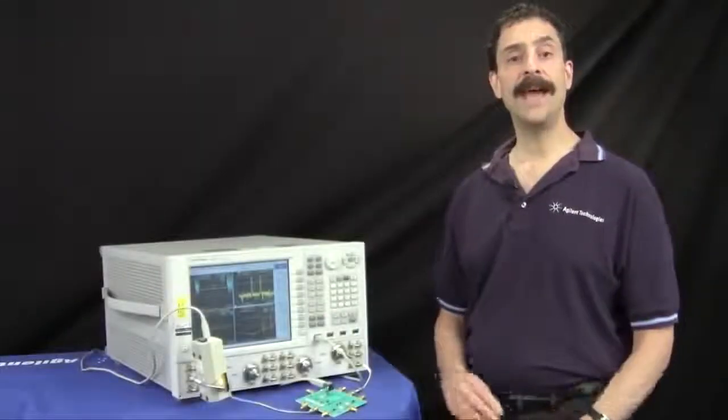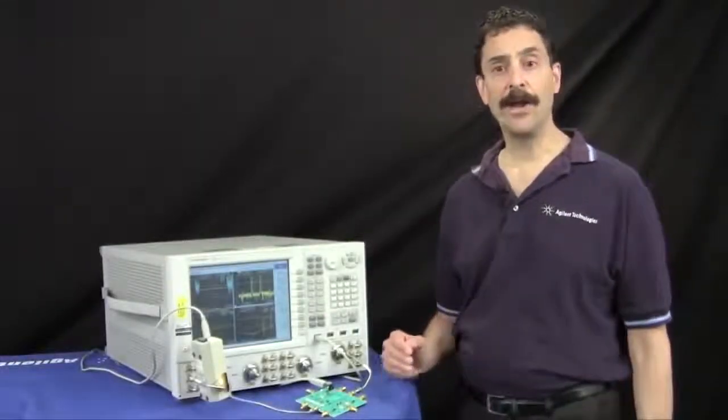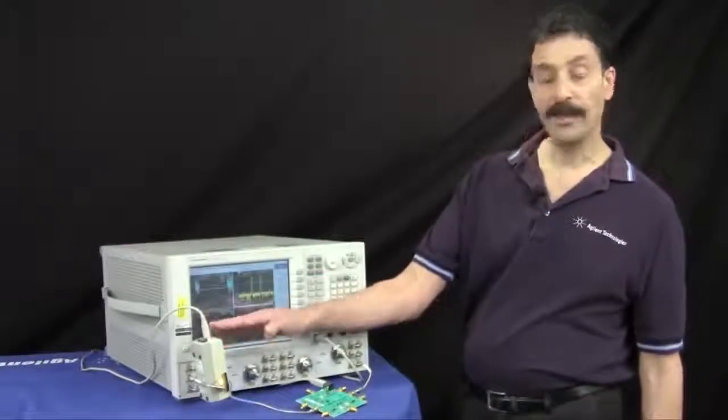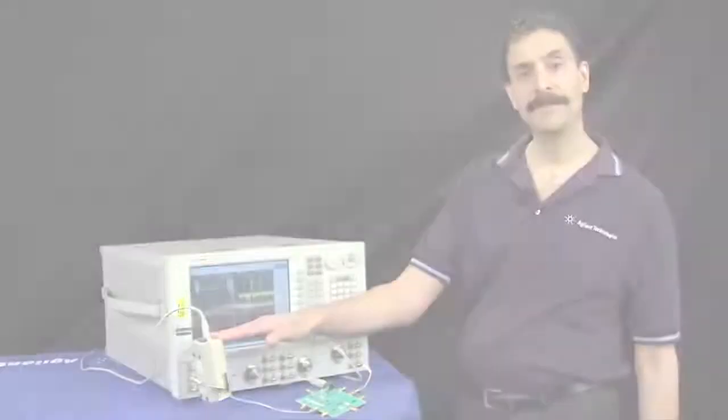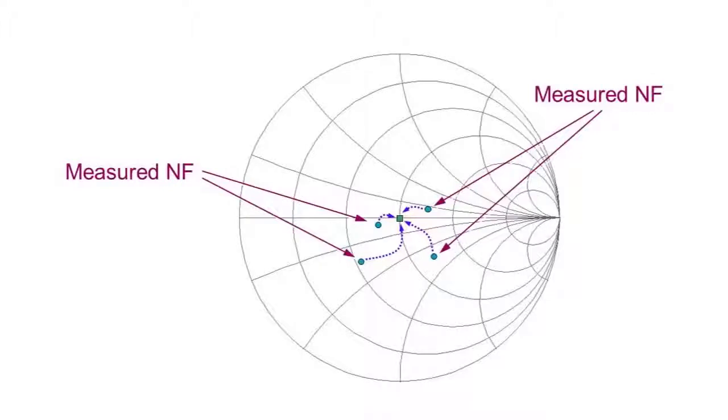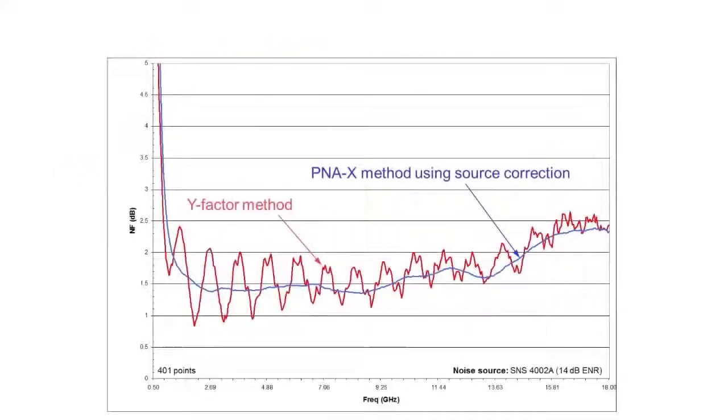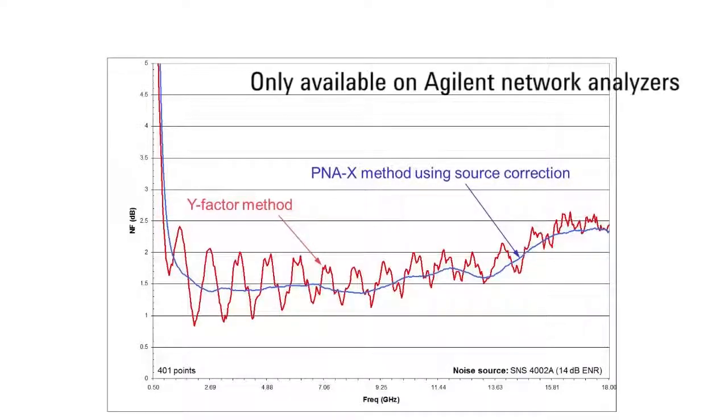The PNA-X corrects for this error by using a standard ECAL module as an impedance tuner. By varying the source impedance presented to the input of the DUT and measuring the resulting noise figures, accurate 50 ohm noise figure is calculated. This technique yields much higher accuracy than assuming a perfect 50 ohm source match, and is only available on Agilent network analyzers.